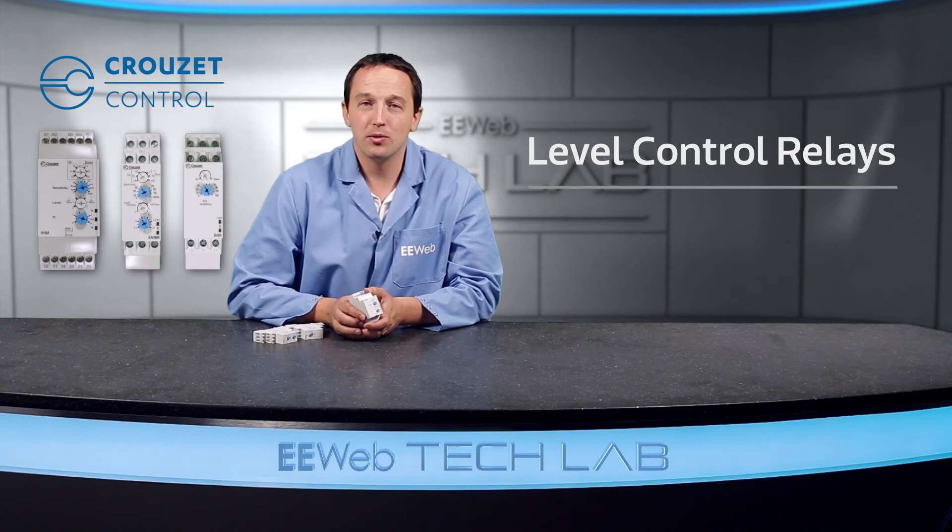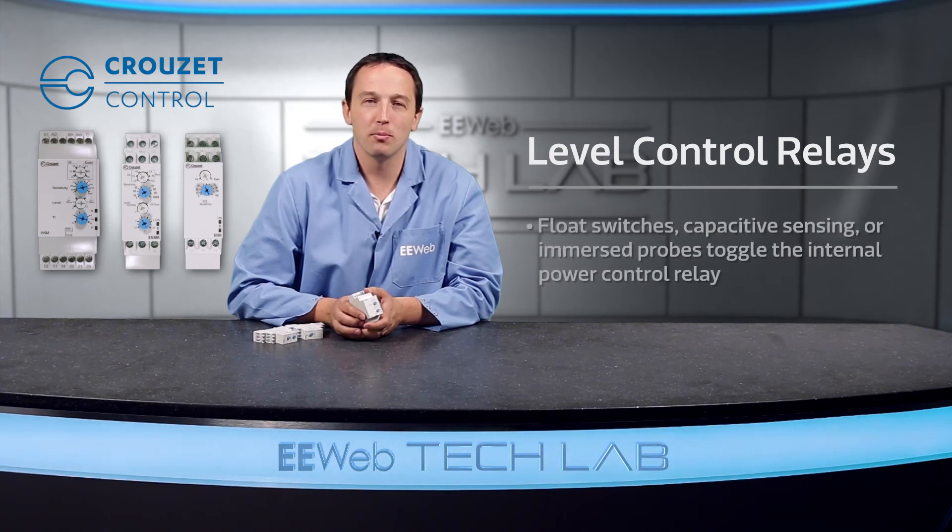Level control with Crouzet relays utilizes float switches, capacitive sensing, or immersed probes to toggle the internal relay, which controls power to the pumps and valves. This controlled filling and emptying prevents pumps from running dry, which often results in downtime to repair or replace the pump.